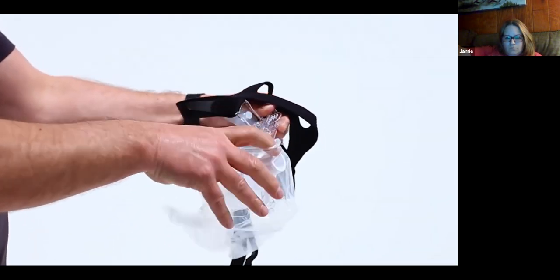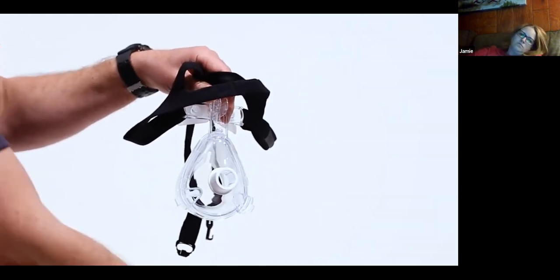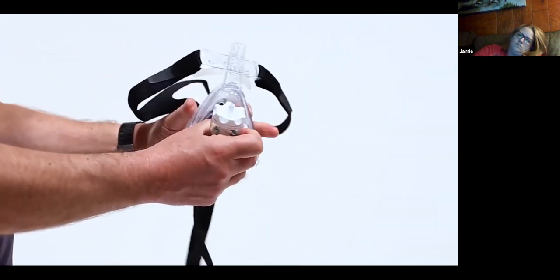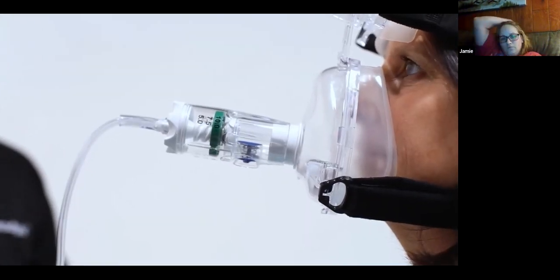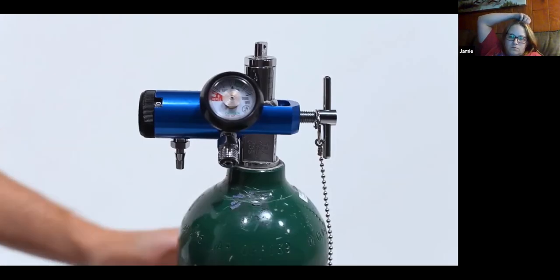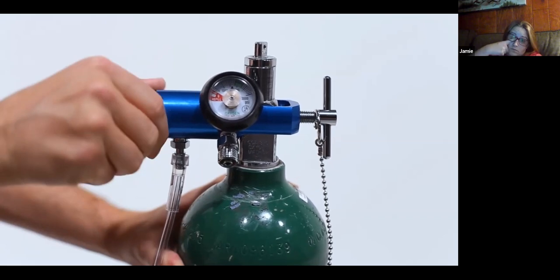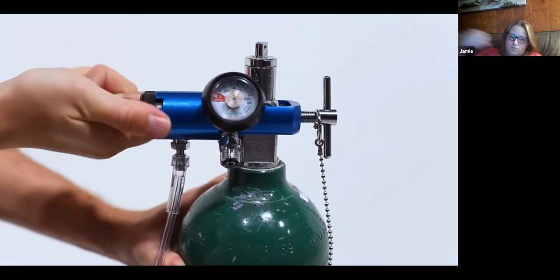The BiTrack ED mask comes in its separate bag. Once you've taken the BiTrack ED mask from the bag, the GoPAP will fit on the hub of that mask. The end of your O2 tubing will fit onto the end of the GoPAP. You will then need to connect your O2 tubing to the low pressure port. After you connect the oxygen tubing, you will adjust your flow settings to 10 liters per minute. Do not exceed 10 liters per minute. Once you feel the flow come through the mask, you are then able to place it on your patient.